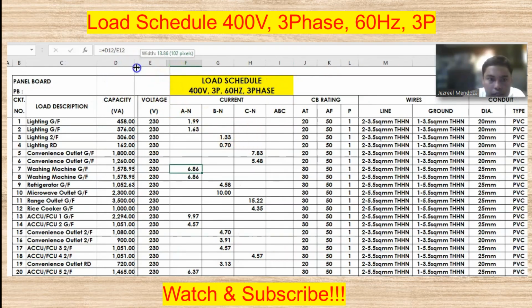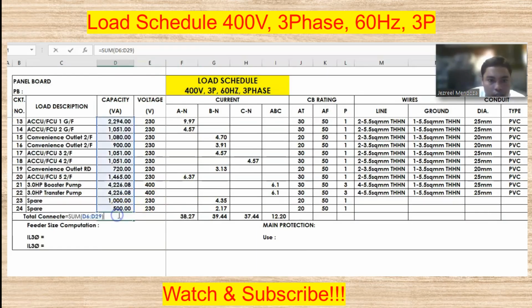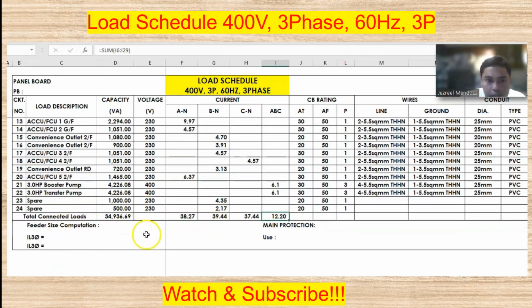Okay, to do that, get the total. Our capacity, that is 34.93 for the line 1, line 2, line 3, then the ABC. Okay, to get the total current, get the highest, that is 39.44. Then that is line to neutral, that's one line only. Let's multiply it by 1. Okay, plus the 3-phase current, that is 12.20.